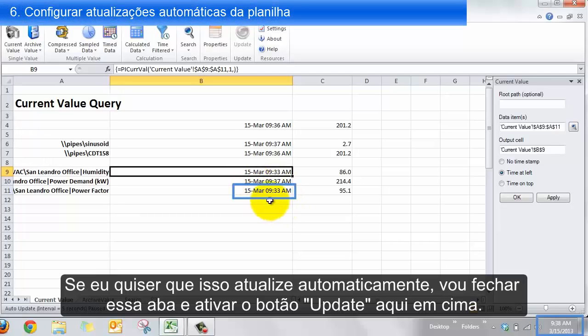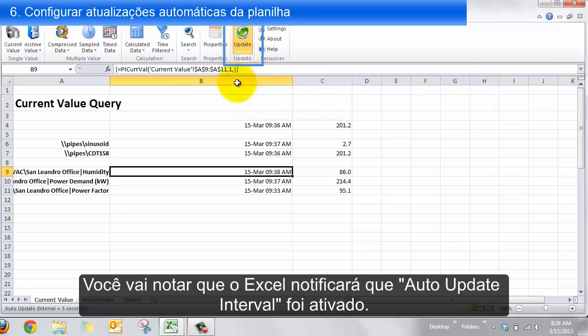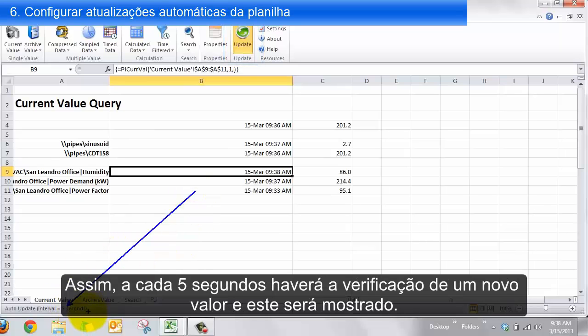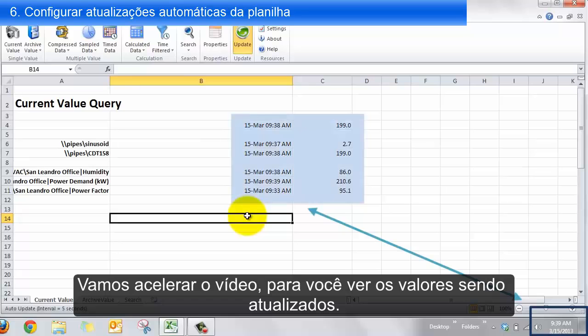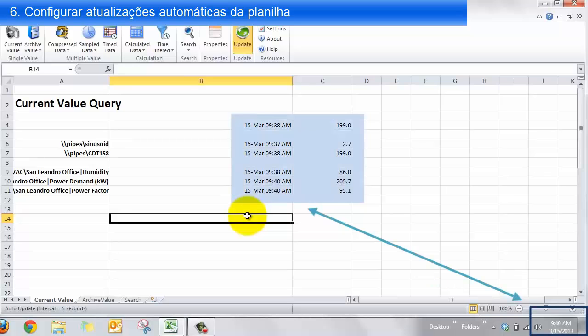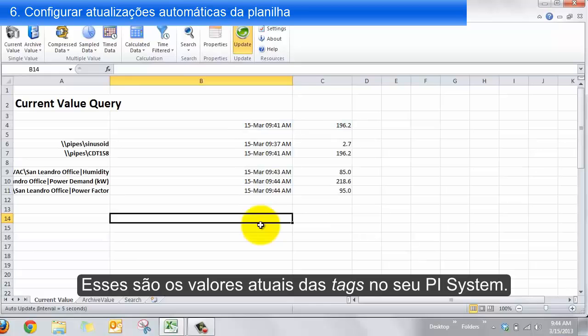If I want these to automatically update as time goes on, I close the wizard and activate the update button. Excel will notify you that the auto-update interval has been activated — this means every five seconds it will check for a new value, and when there is one, it will put it out on the sheet. We'll now fast-forward the video so you can see updates coming in over a few minutes. And that's the current value query — it shows you what's currently going on for a data point in your PI system.